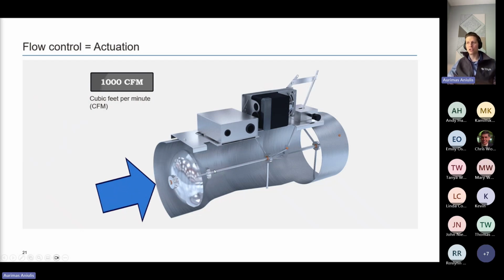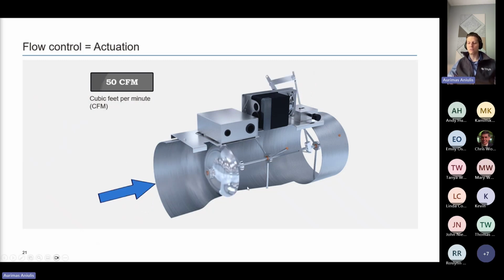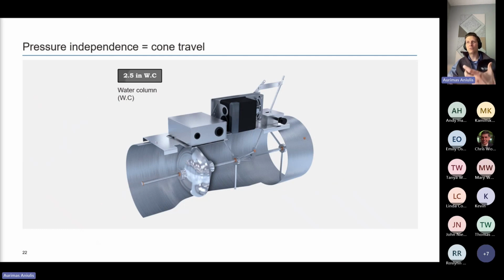Again, Venturis are position-based control, no sensor in the airstream. Now, once it arrives at its CFM position, what happens is nothing else moves other than the cone spring assembly, and it just slides and glides on that cone shaft based on duct static pressure fluctuations. So if you commanded this valve to 500 CFM and it's within its operating pressure range, regardless of the duct static pressure swings, and we're showing here a full swing from 3 down to 0.6, it will maintain your 500 CFM output, right? Because this is the way this technology works due to this mechanical cone spring configuration.